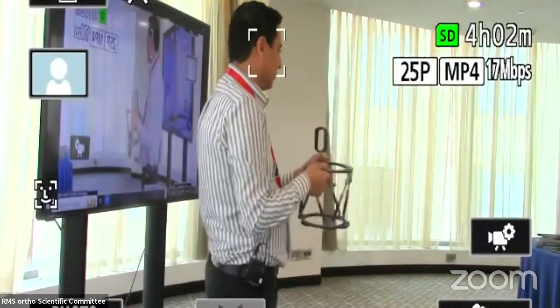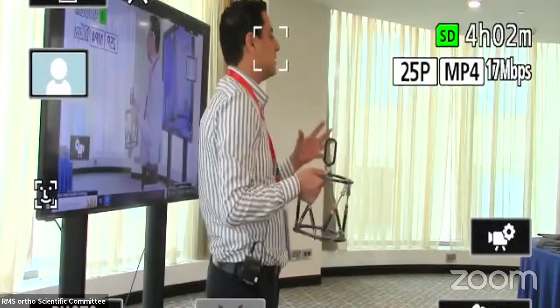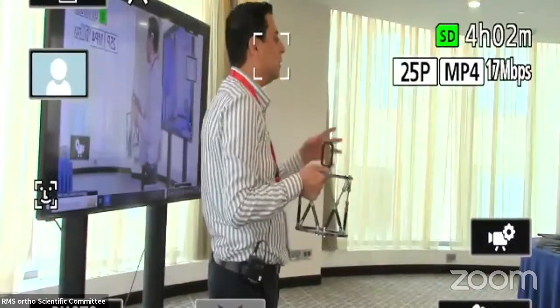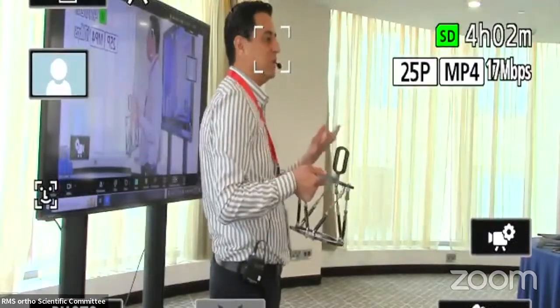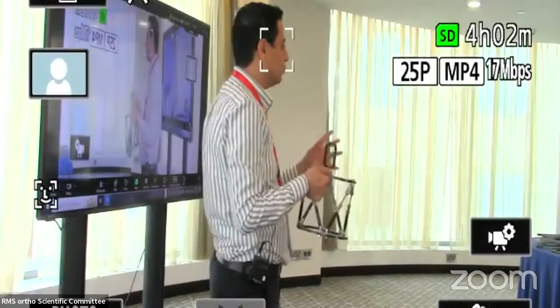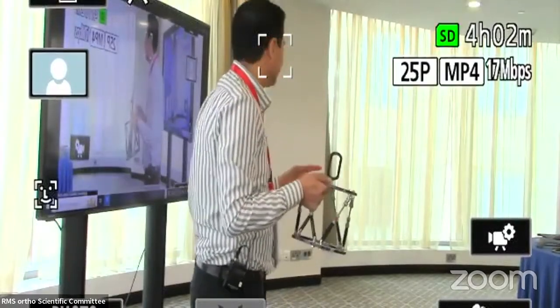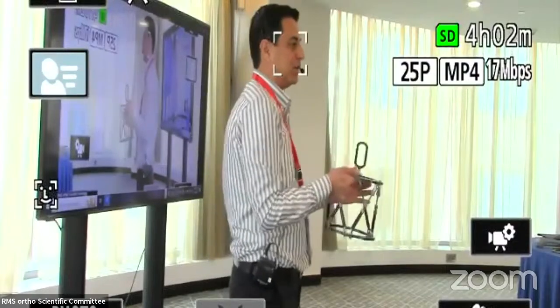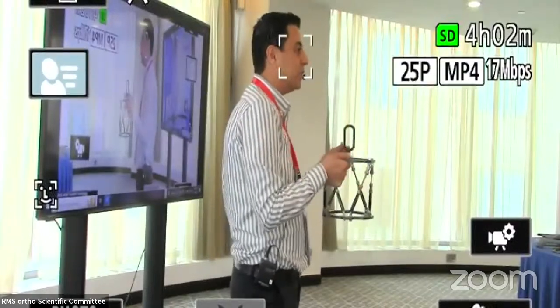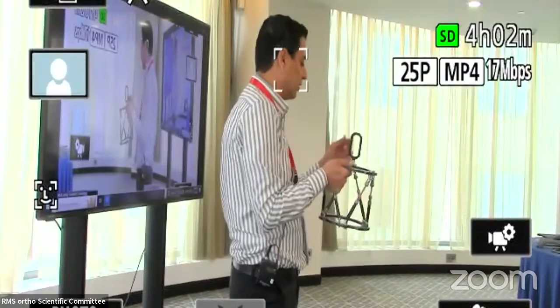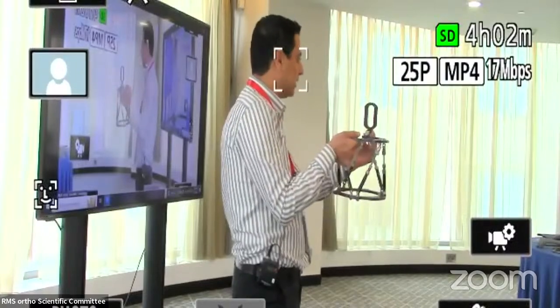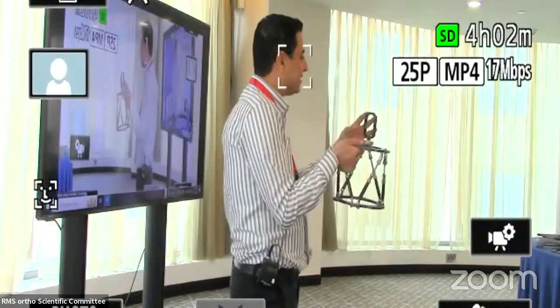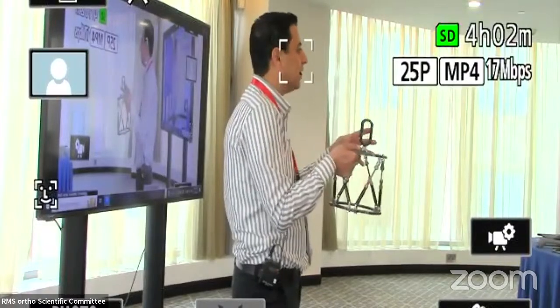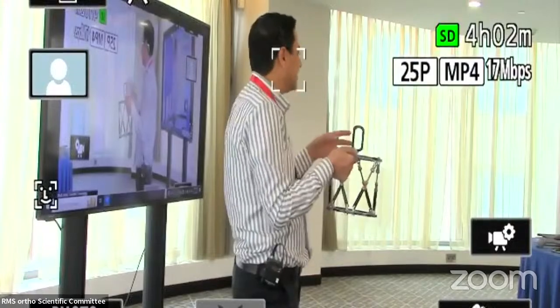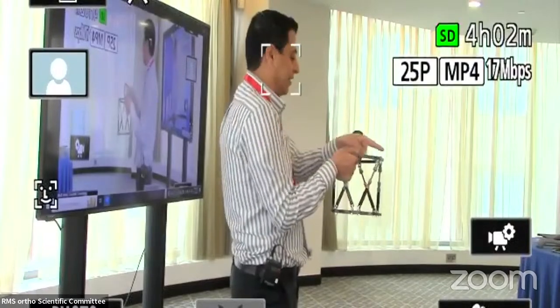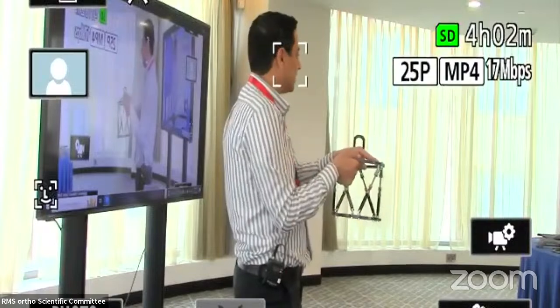And the last thing about this frame is the beacon. This is the new thing about the smart TSF. We started to use the smart TSF less than a year ago. Before the smart TSF, we were using the regular TSF, which is different and does not use the beacon. What is the beacon? It is this small device here. It will tell the X-ray what the parameters and the calibration are, and exactly what the relation of the bone is to the master tab and everything.